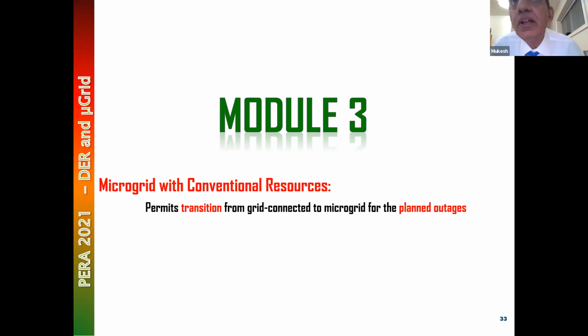Module 3 is a microgrid example. Now this example with conventional sources is a very complicated example. Also, in this case, the system was not built for microgrid operation. It was built to connect distributed energy resources for peak shaving, for local supply, for energy purposes. The original intent of connecting distributed energy resources in this part of the system was not a microgrid. We subsequently made incremental changes to allow it to operate as a microgrid, and that's what I'll talk about, because it was not originally planned for microgrid operation.